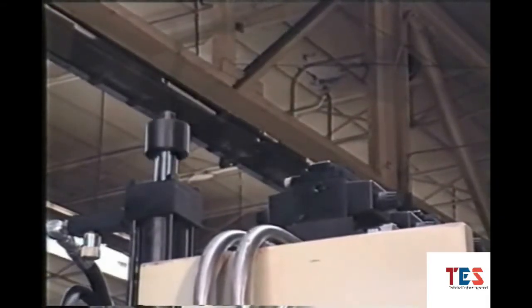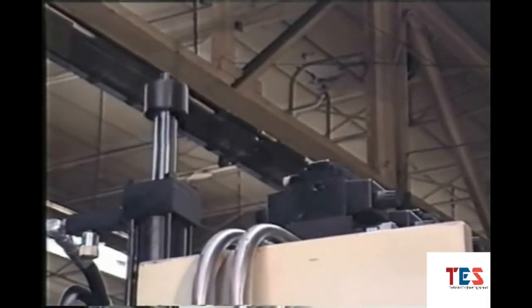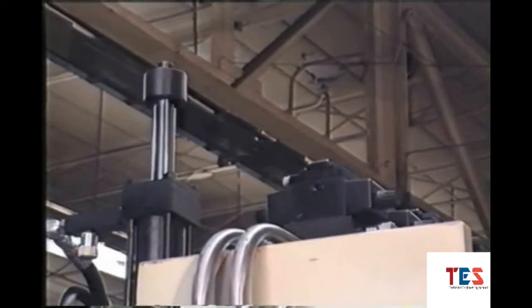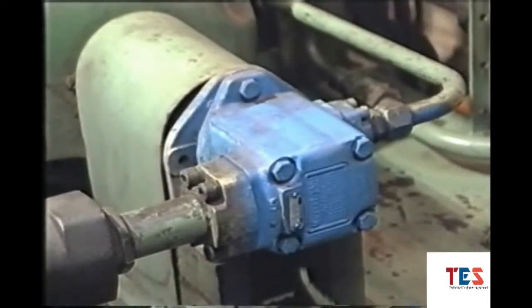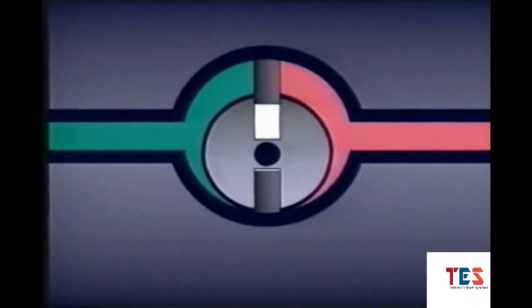The work a system can do is usually measured in horsepower. Industrial hydraulic systems use positive displacement pumps in which the output is the same for each revolution of the pump. As the pump turns, fluid is moved or displaced from an area of increasing volume to an area of decreasing volume.